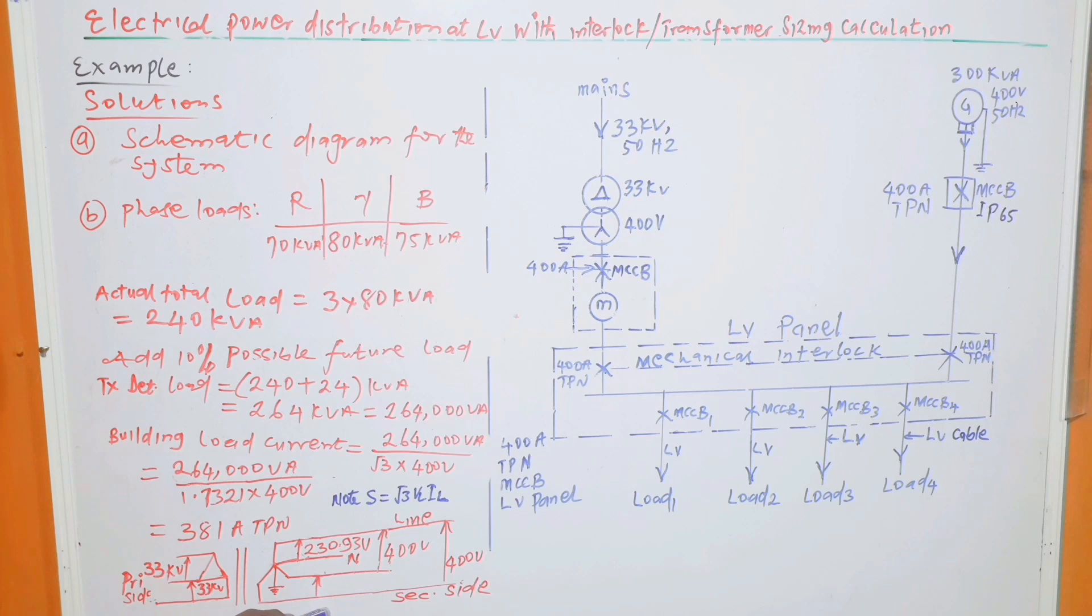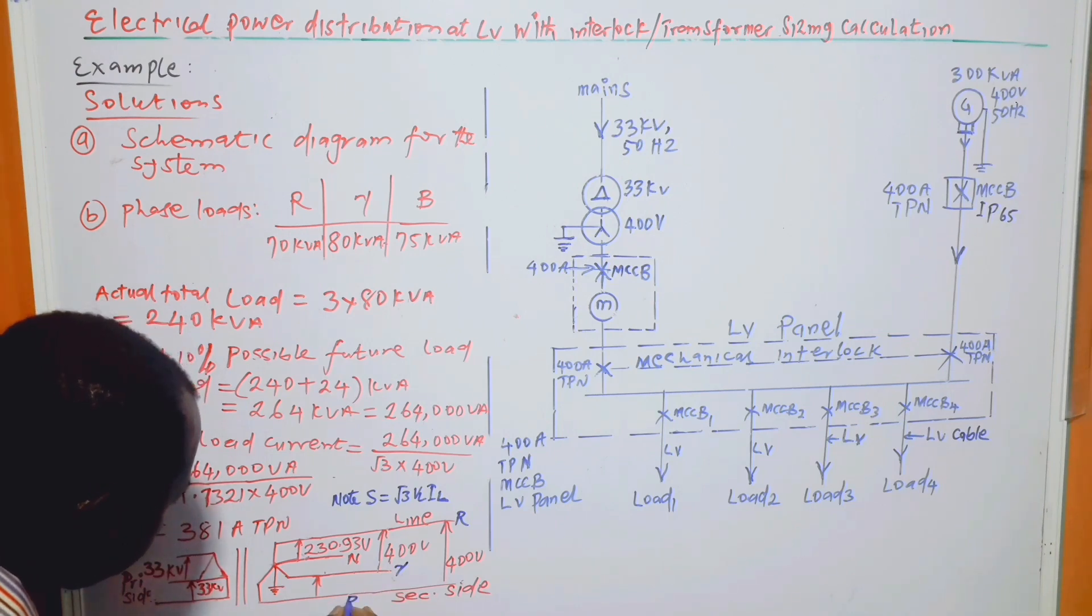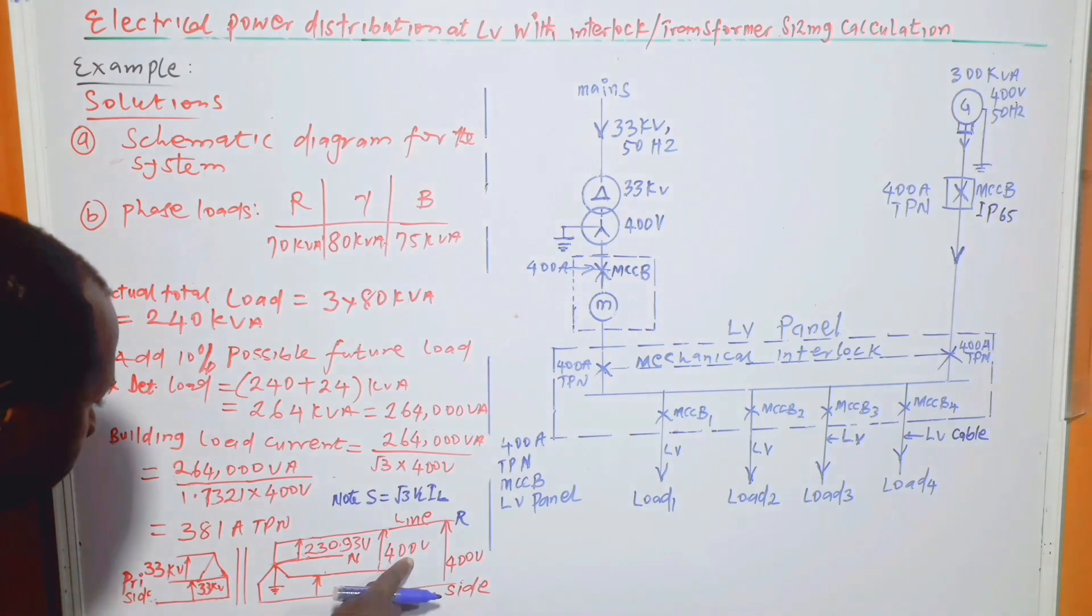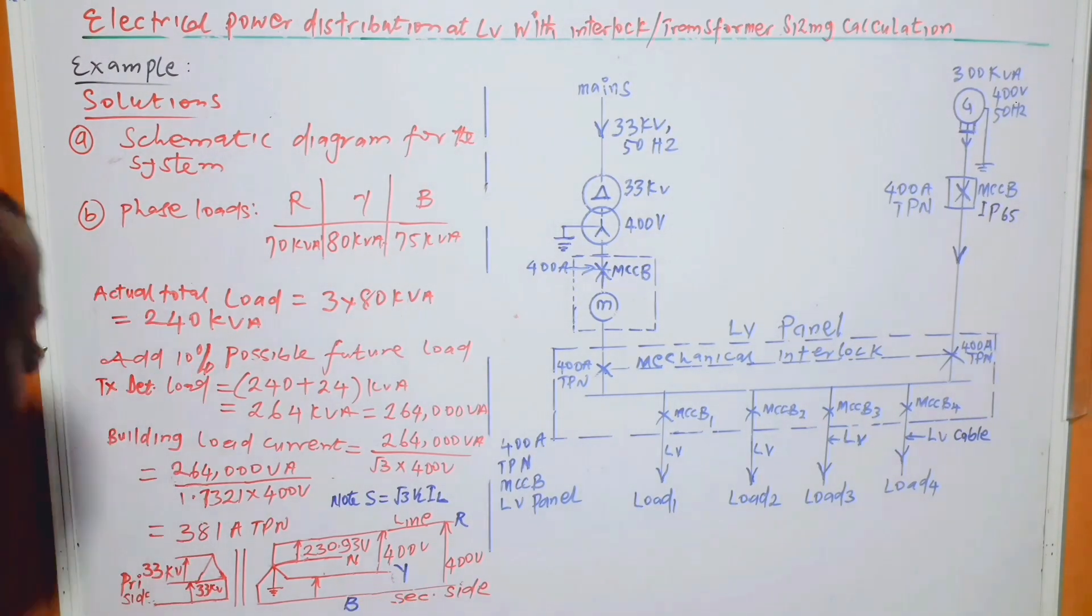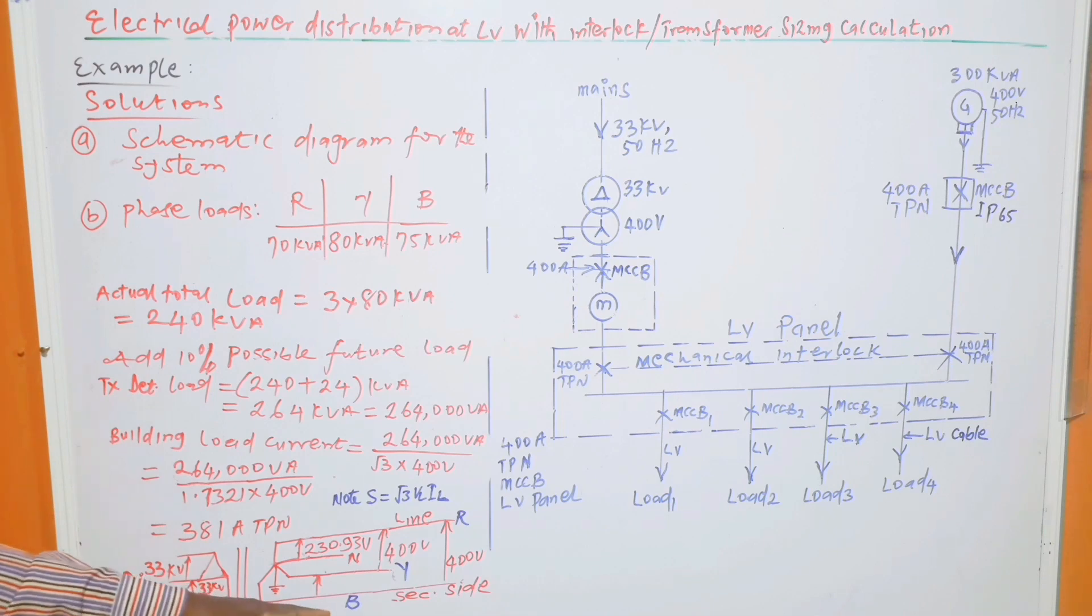So the current flow in this phase is also 381, and also in this phase is also 381. So actually, we can call this one the red phase, and this one will be the yellow phase, and this one the blue phase. So this is the secondary side, and this is the primary side. We have 33 kV line to line. And that is the answer to the B part of the question.